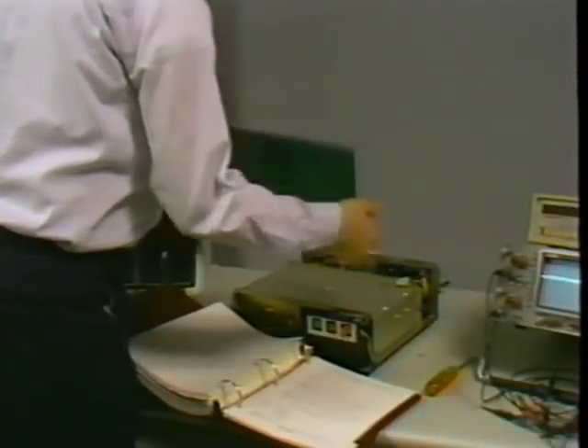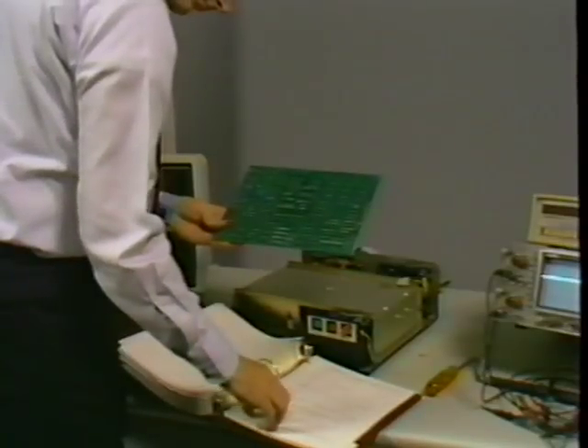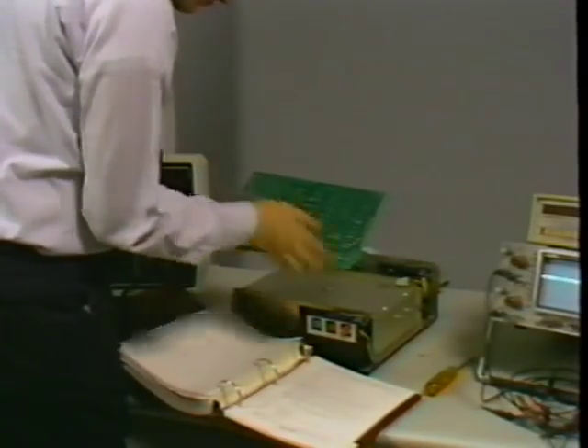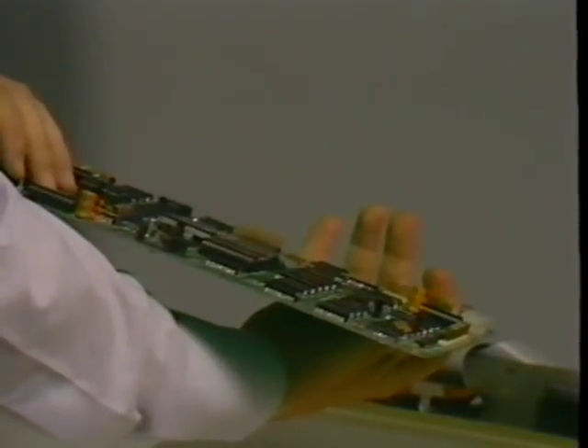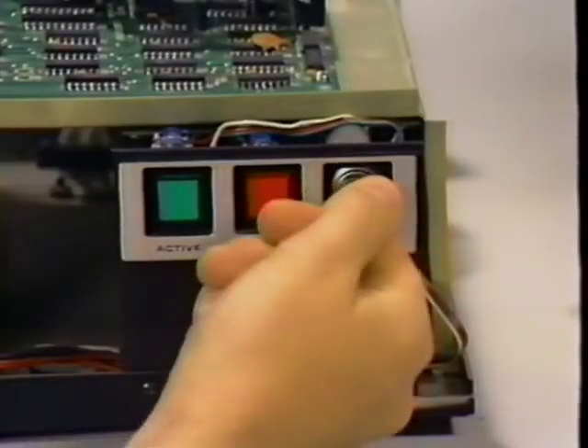Although not all controllers have all adjustments, there are some rules that apply to all hard drive alignments. Always check the hard drive for mandatory modifications. These can affect the results of your alignment and the reliability of the drive. For the best performance and customer satisfaction, make sure that all modifications are done. Warm up the hard drive for at least 30 minutes before alignment to accommodate heat-related media expansion and component drift. A drive that appears correctly aligned when it is cold may not operate properly when it is hot.